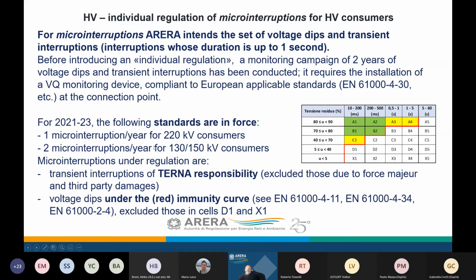And in case of a higher number of micro interruptions, either transient interruptions or voltage dips in a year, these specific consumers are protected by an individual compensation. I suppose this is the only case in Europe in the regulatory framework to introduce such a compensation for voltage dips so far. Of course, only interruptions under Terna's responsibility are under the standard, so dips related to force majeure or to the emergency phase of the system are excluded, and only voltage dips under the red immunity curve are included in the standards.